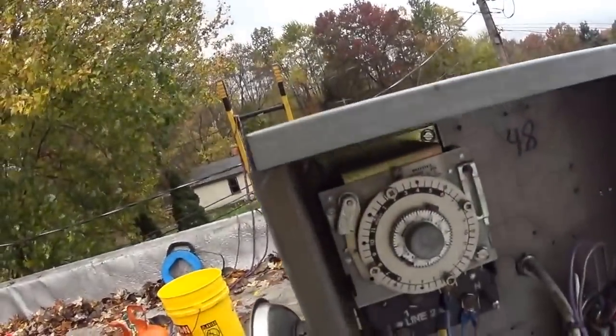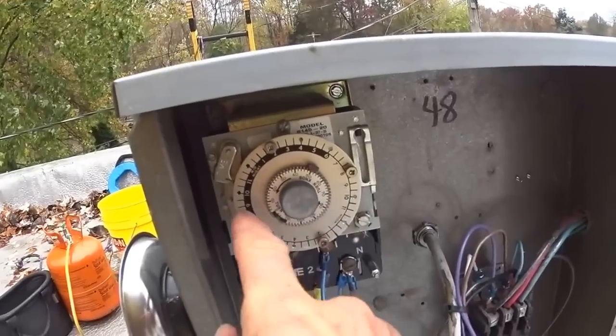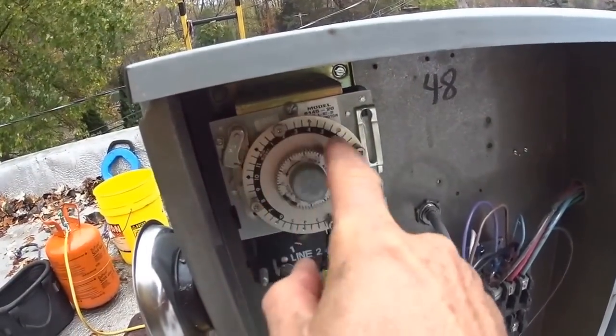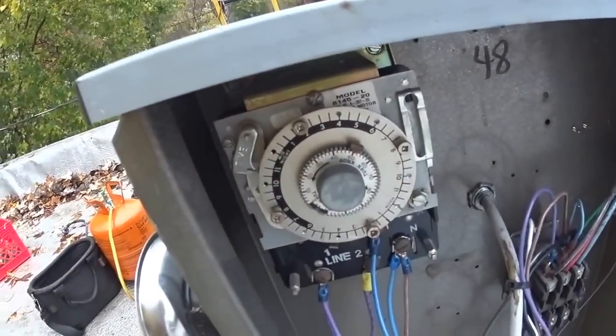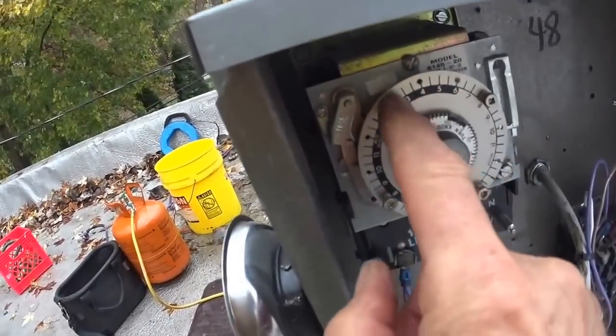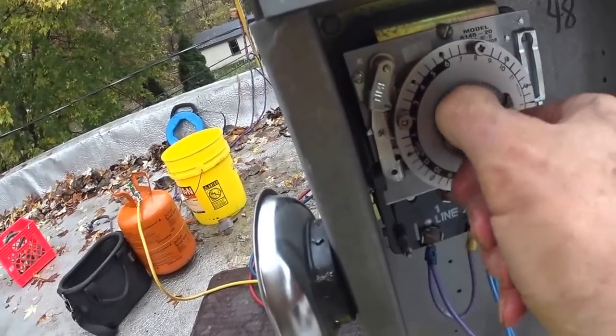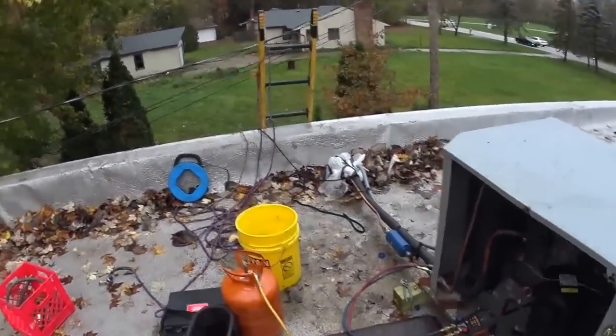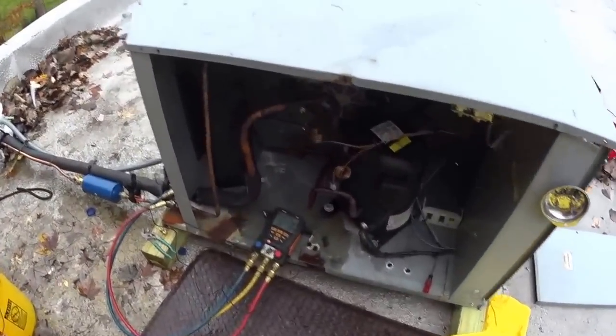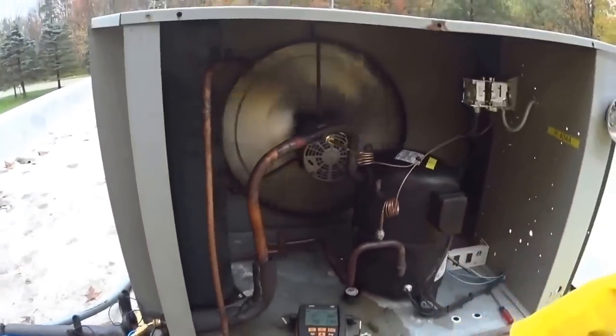The time clock is a 24-hour dial. There are four defrosts in the 24 hours, and each defrost lasts 15 minutes. I'm going to turn this when it lines up with the pin. It just clicked on the defrost, and in a few seconds you can see the pressure pumping down now.